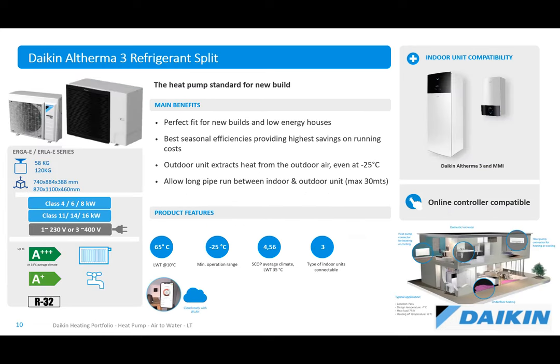Refrigerant splits. So this is the alternative to a monoblock. You can see that the outdoor unit is more compact, and that's because your hydraulic components and your PCB boards, your backup heater, heat exchanger are all built in to the indoor unit. So when you look over here at this tall indoor unit with the black control panel on the front, this is what we call an integrated indoor unit. It houses your domestic hot water storage, so you can have 180 litres or 230 litres of hot water storage. This smaller unit beside it, which looks like a gas boiler, is a wall-hung version. So this wall-hung unit houses all the hydraulic components, heat exchanger, backup heater, etc., and allows you to put a separate cylinder in a different location. And again, this is just giving you different options for how you manage the location of your indoor units. Refrigerant splits generally give you the best efficiency.